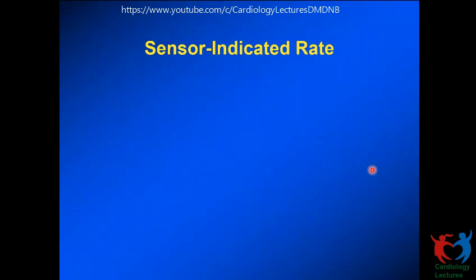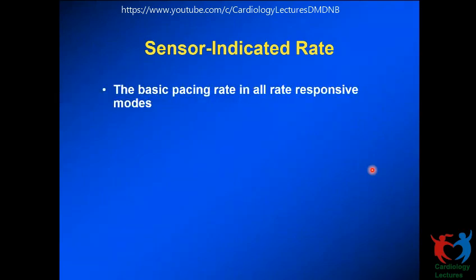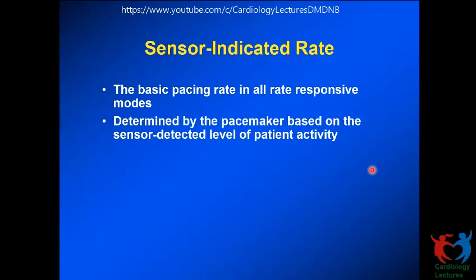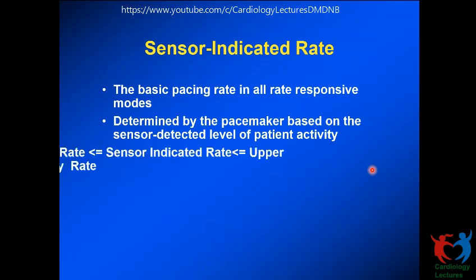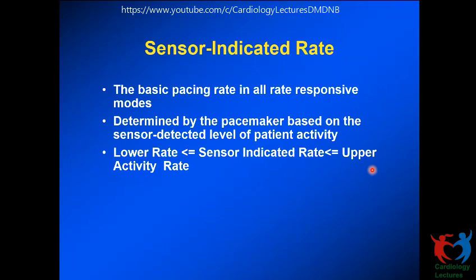And if you are implanting a rate response pacemaker, then the concept of the sensor indicated rate comes in. The time is, yeah, we still have about 10 minutes. Sensor indicated rate. You program a lower rate, and you don't want to pace the heart at a very fast rate when the patient is physically active. So you want to put a limit to that. That's your upper sensor rate or the upper activity rate.